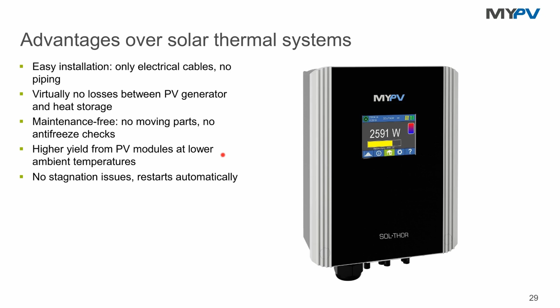This is due to the fact that we have decentralized hot water heating, so we can use solar power directly at the point of use in the apartment, and we do not lose anything on the transmission line. A hydronic system would mean there is a ring main pipe which pumps hot water 24/7 to every apartment, and this is not required anymore, because on these ring main pipes you use megawatt hours of energy during the whole year, and these are losses completely avoided here with wires instead of pipes.